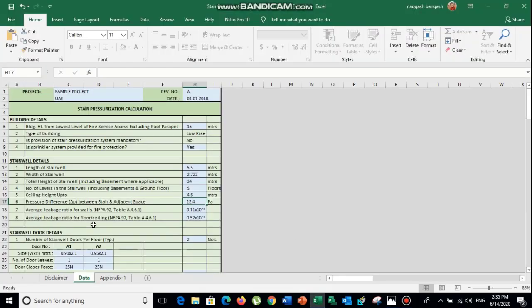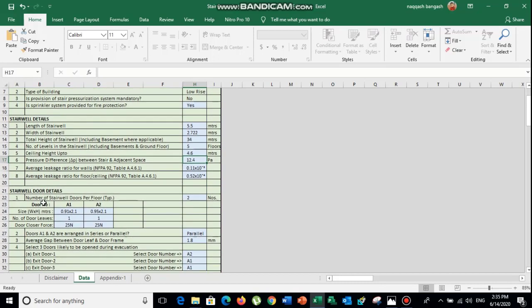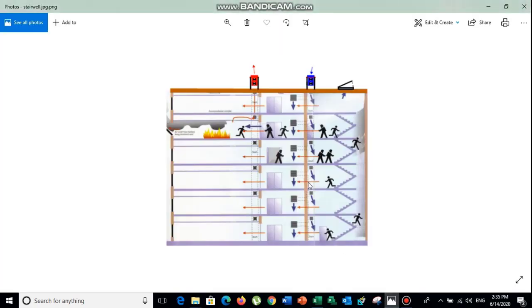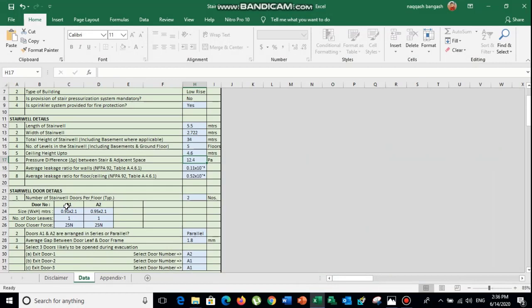The average leakage ratio for walls is already provided by NFPA 92, specifically Table A 4.6.1, according to the National Fire Protection Association standard. The average leakage ratio for floor-ceiling is also provided by default from NFPA 92 Table A.4.6.1. Next are the stairwell door details — if you have one door, you provide the size of the door in meters, the number of doors, and the force required to close the door.